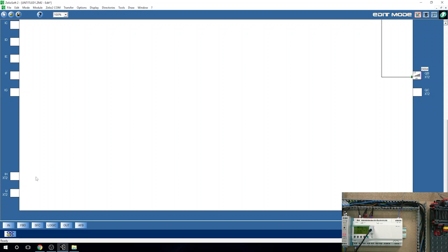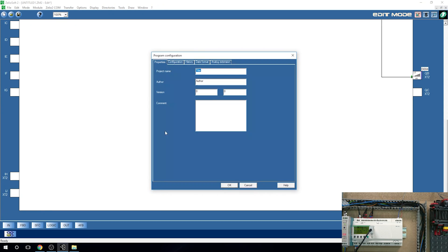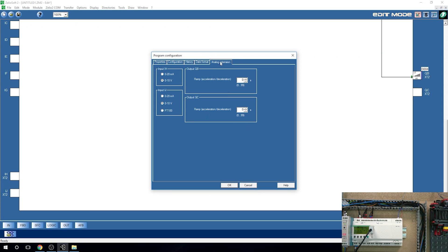As I said, the PT100 is an IJ. So before we can even start working with anything, we need to configure that IJ to be PT100. If you click on this program properties, go into analog extension, and select PT100. So that's the one we need to make sure is selected for the controller to understand that they need to work with that kind of scaling.